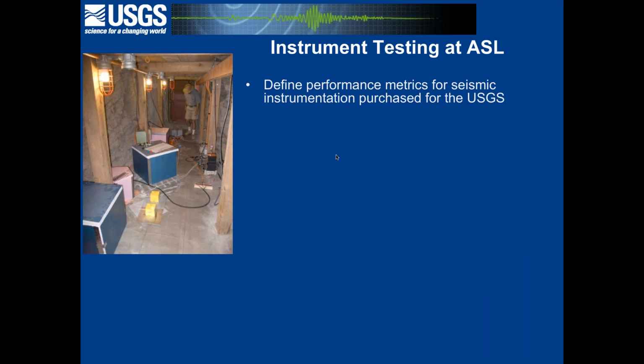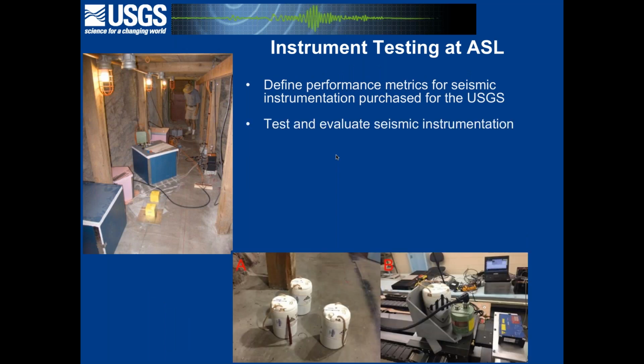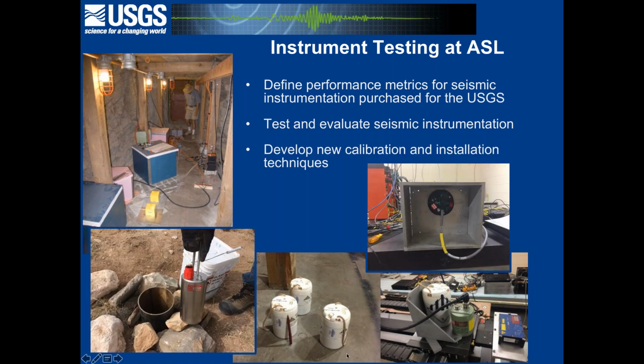So what do Adam and I work on? We are part of the instrument testing group at ASL. We define performance metrics for seismic instrumentation purchased by the USGS. We test and evaluate seismic instrumentation. Here again are the Fairfield nodal sensors, and this is an example of our horizontal shake table. So we're trying to drive the response of this instrument here.